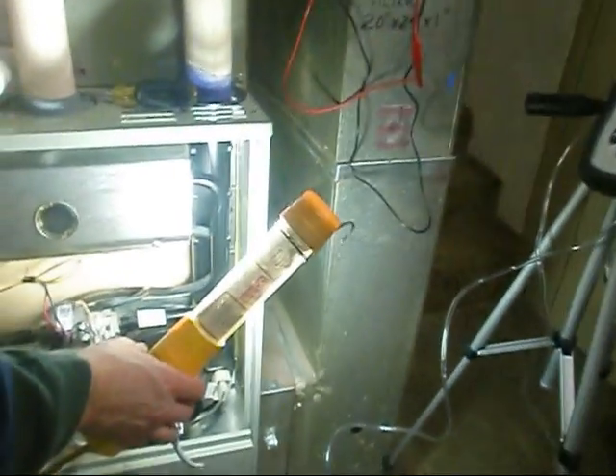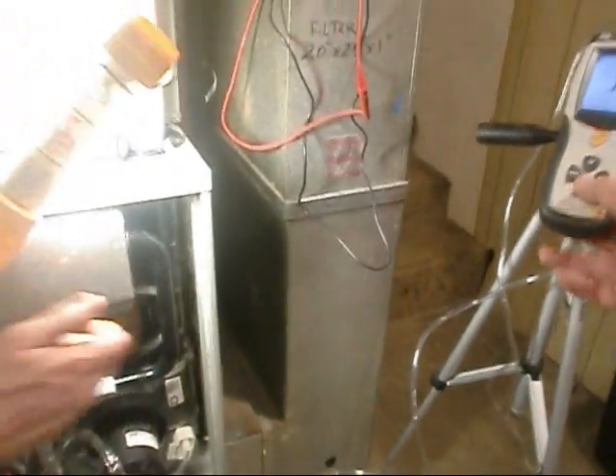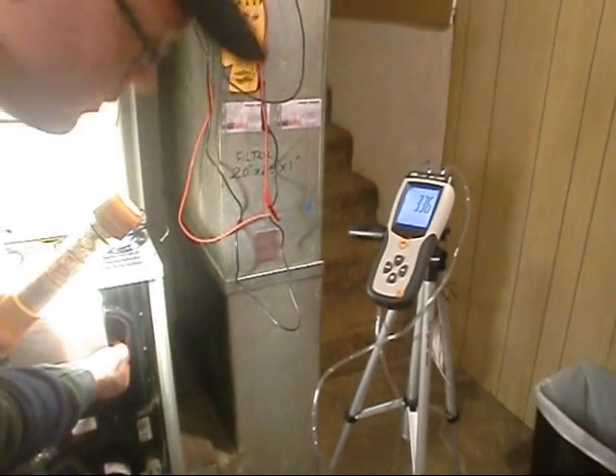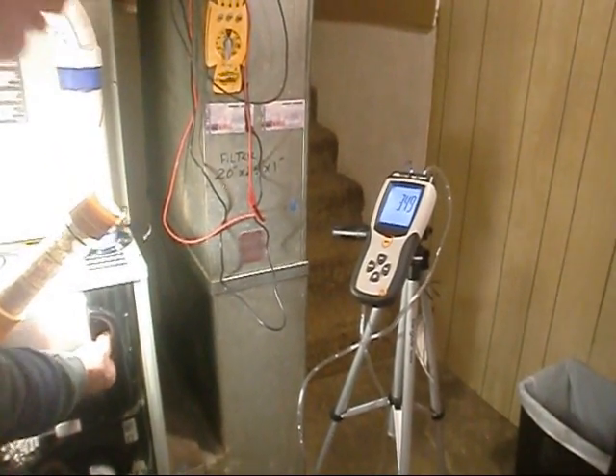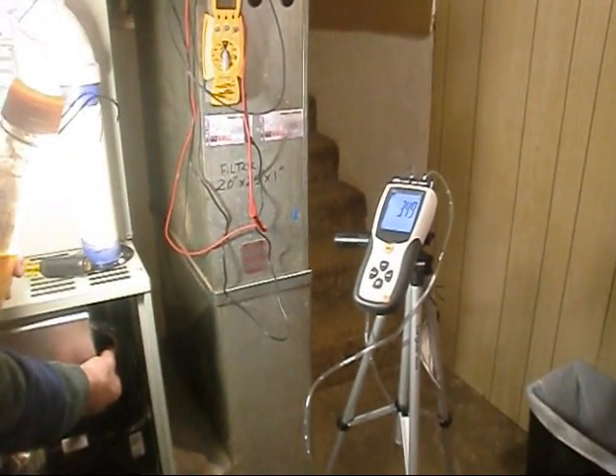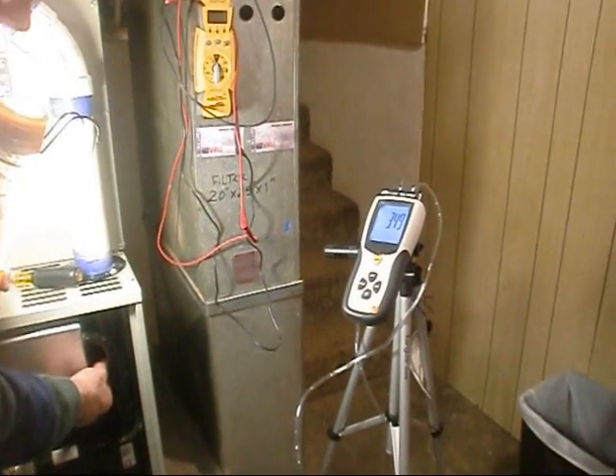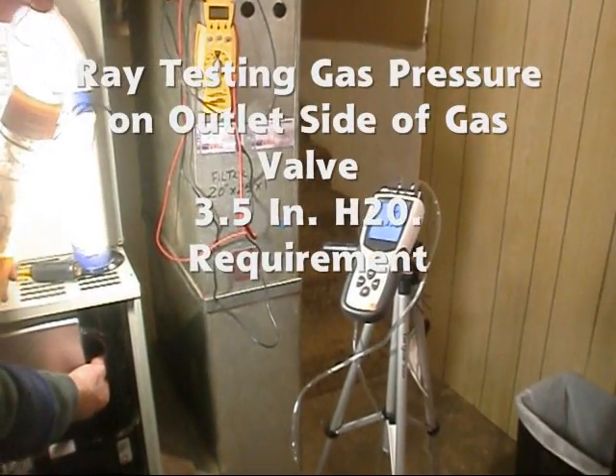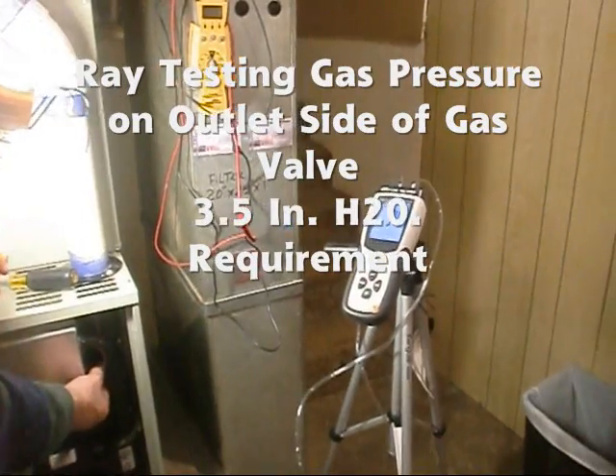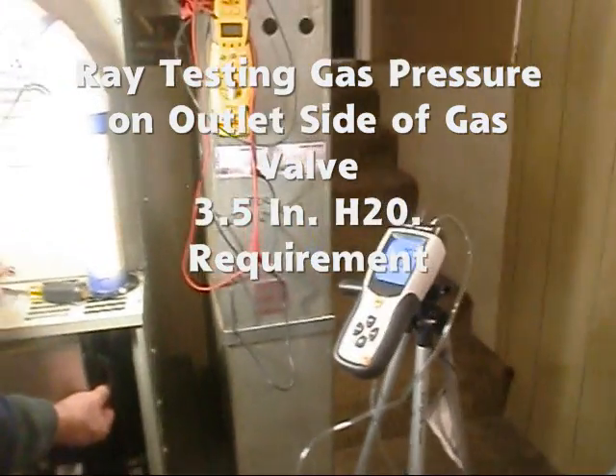Take your light there, shine it in there. Do you see that going into the burner box right there? Oh yeah, it's connected to the gas. Let's get our light on here and watch you remove it at the same time and see what it does. We were looking for 3.5, I think I had 3.49 a while back. Yeah, it went right up to 3.5, or 3.49. You can actually look back at my video when I adjusted that. You have to be at atmospheric pressure when you do a 90% furnace.